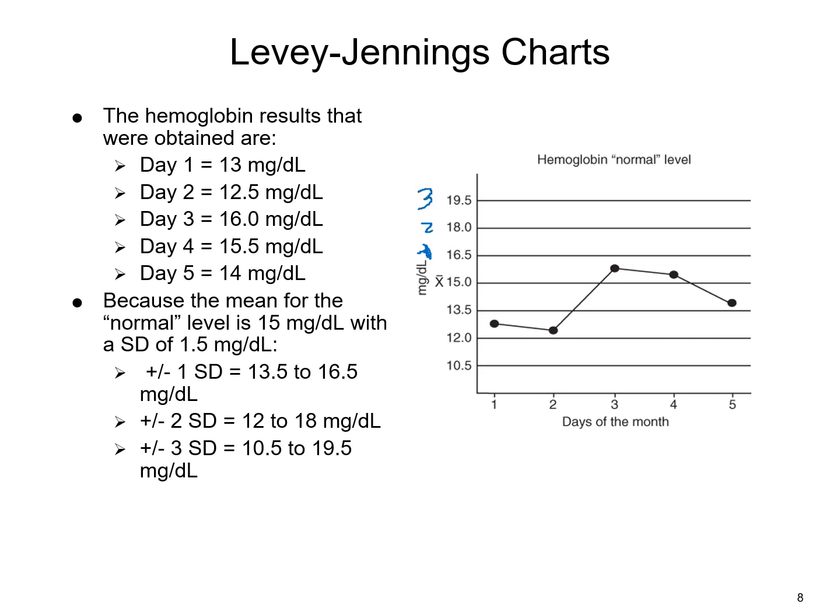Again, here's our mean at 15.0, and then this is 1 standard deviation, 2, and 3. Now, when I actually plot my values, sometimes it helps to kind of color code it. Not always, but we know our mean is there. So looking at our Westgard rules, typically anything within 1 standard deviation is good. So 1 standard deviation, I kind of visualize that to still be within the green. And then you kind of have a cautionary period at 2 standard deviations.